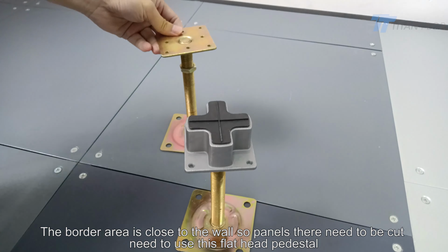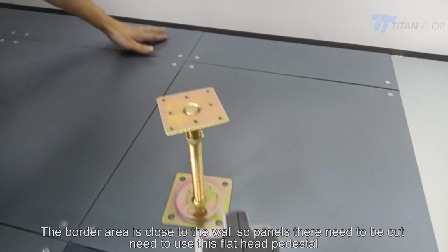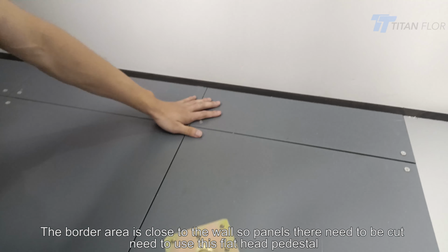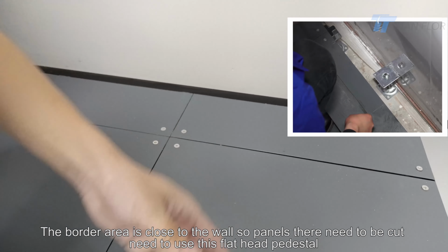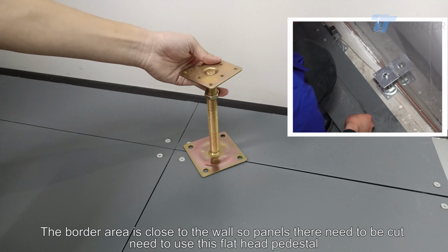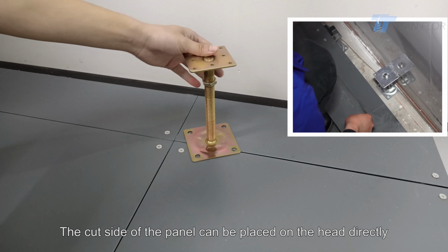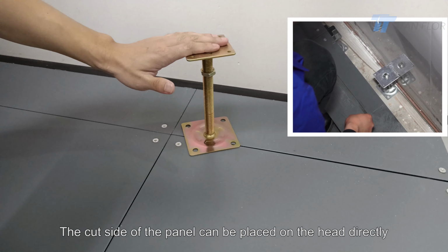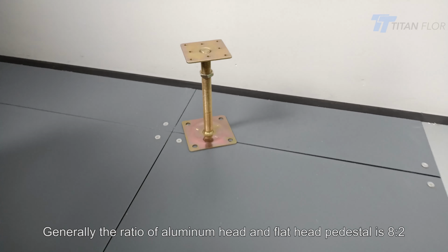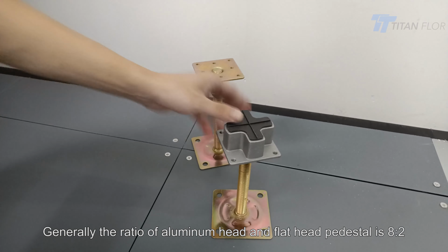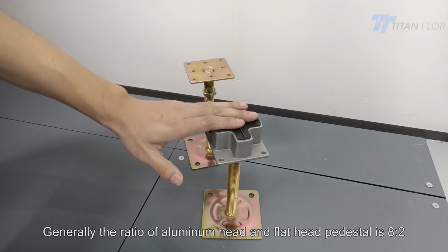The border area is close to the wall, so panels here need to be cut, and need to use this flat head pedestal. The cut side of the panel can be placed on the head directly. Generally, the ratio of aluminum head and flat head pedestals is 8:2.